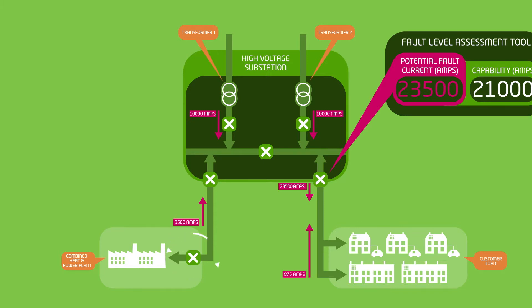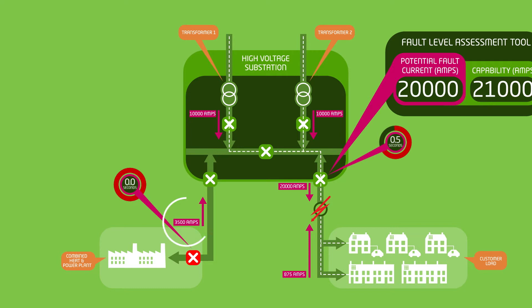But if the installed circuit breaker was managed by Electricity Northwest via a commercial agreement with the customer, we could set it to trip after the fault, as we did with transformer one in the previous example. Removing the fault current from the CHP and enabling the existing high voltage circuit breaker to operate within its capability.